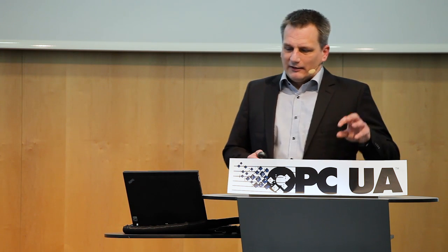So there's an OPC UA object, which is a representation of a data point or some processed value, and it has a variable, and it can have methods, and it can have events and fire events, and this is a complex object. And as you can see, the variables are the functionality we had before with OPC data access and historical data access. And the events, that's what we had and called OPC alarms and events. And the commands are method invocations of those kinds of objects.